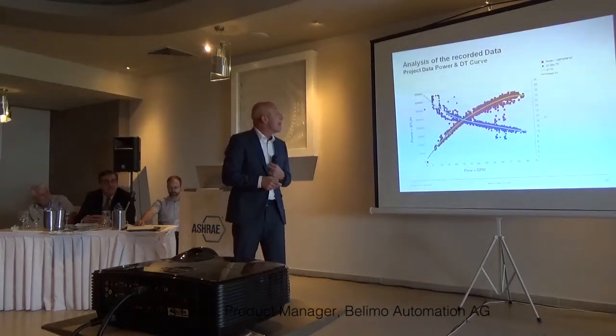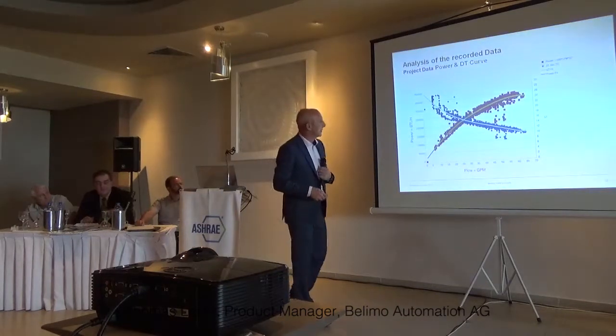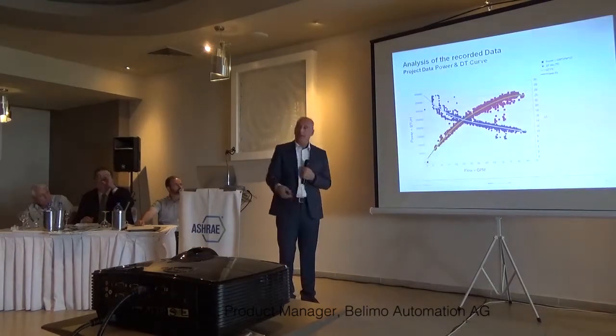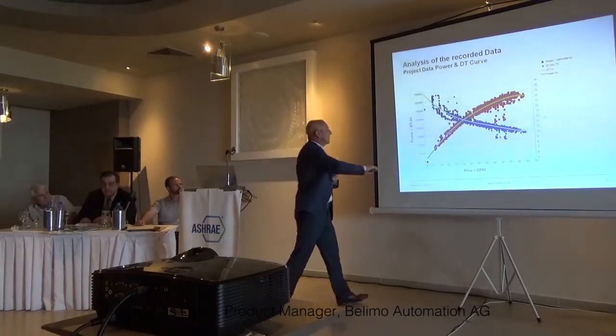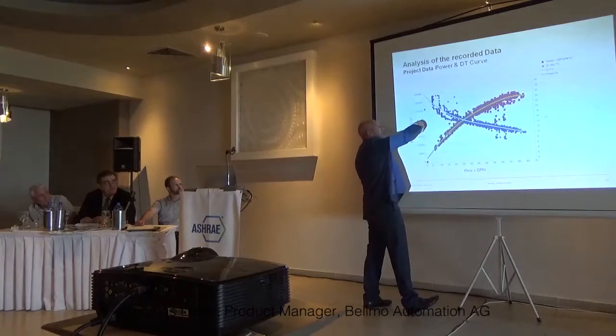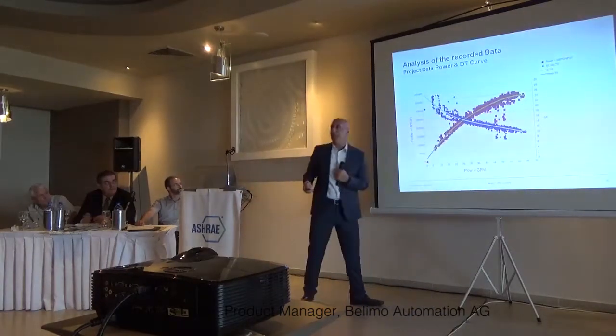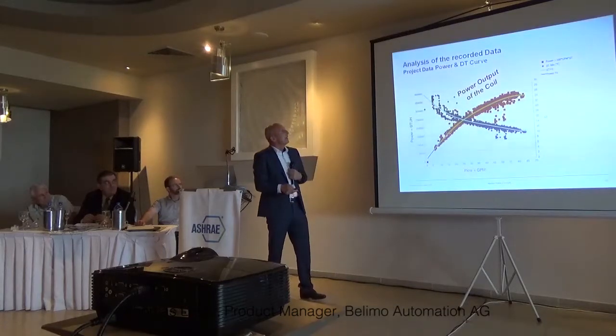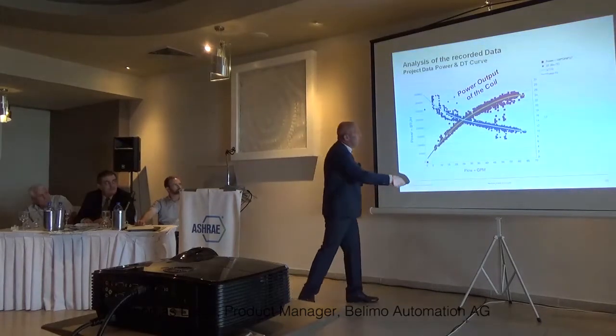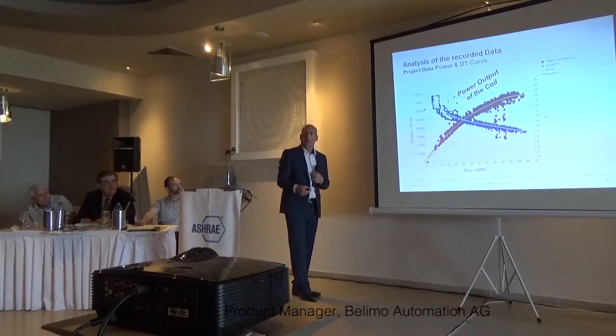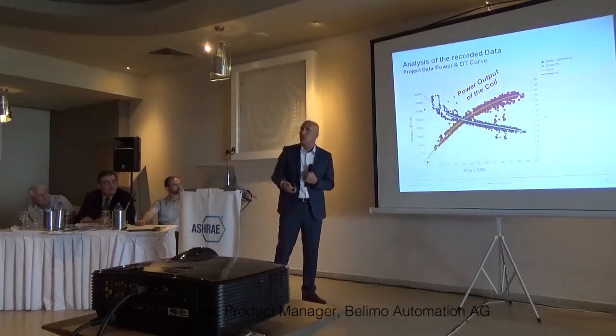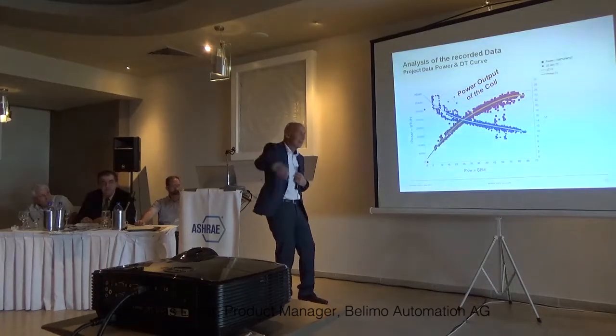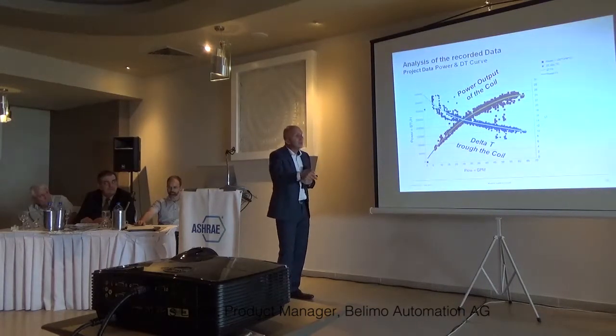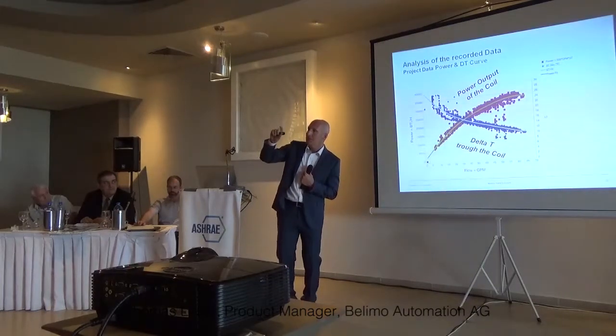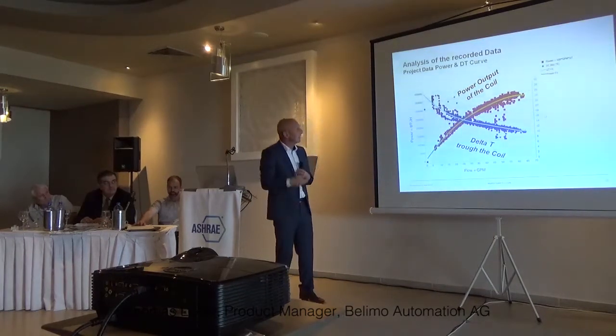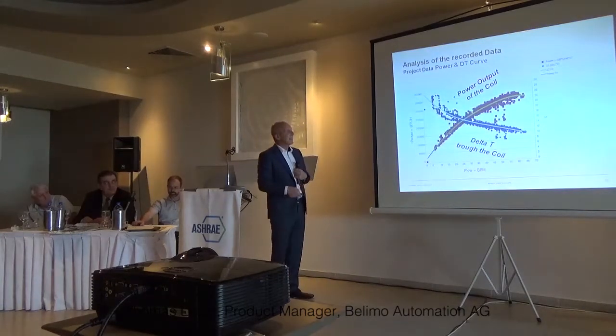When we do data recording, you will get this kind of data. By the way, these are real data. This is the performance curve of my fan coil, of my air handler. This is the curve of the delta T. What you can see here: the more flow I give, the bigger the output of my coil. However, the more flow I have, the more my temperature delta will shrink. This is a physical thing, and you cannot deny this.